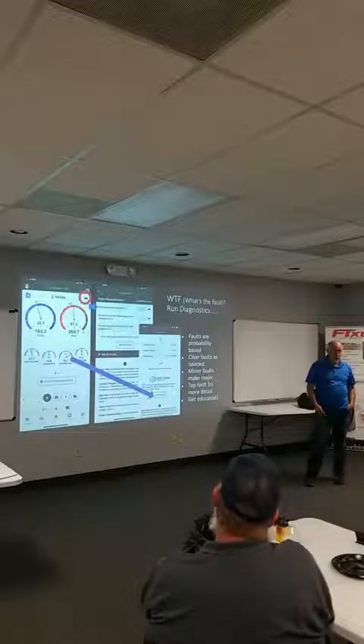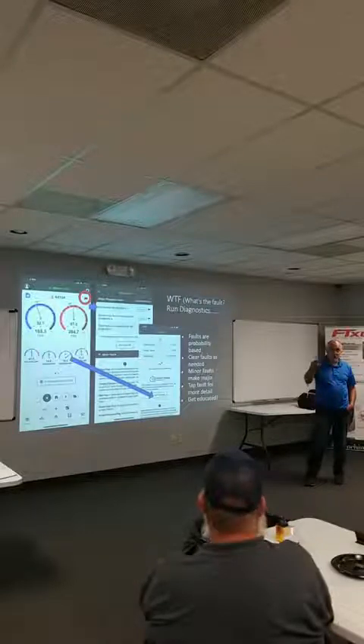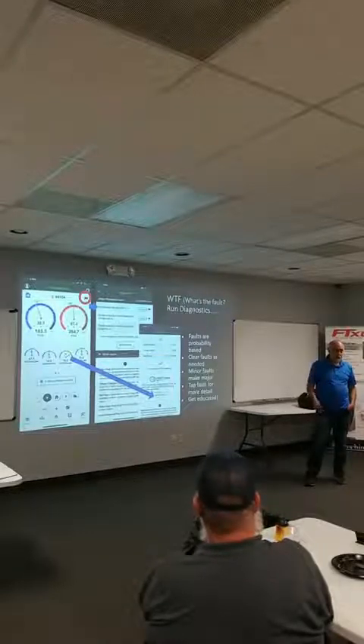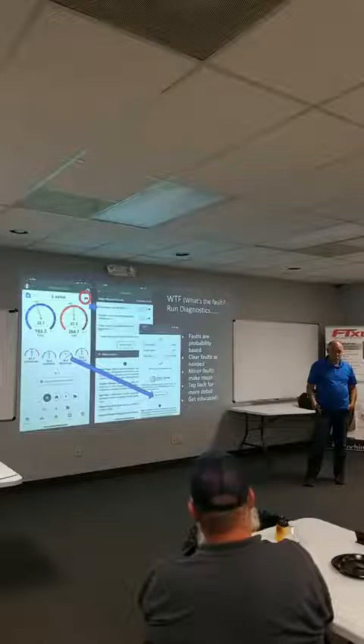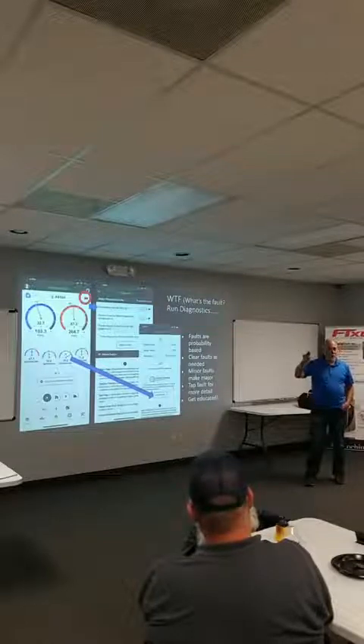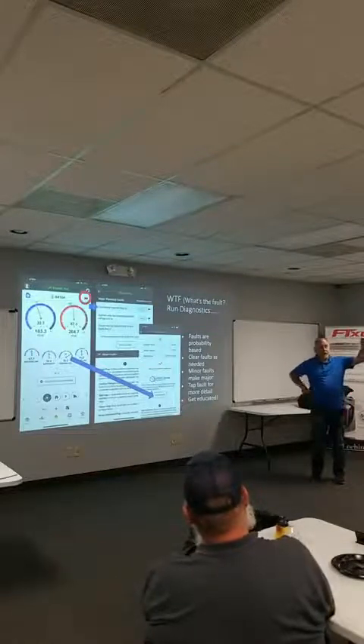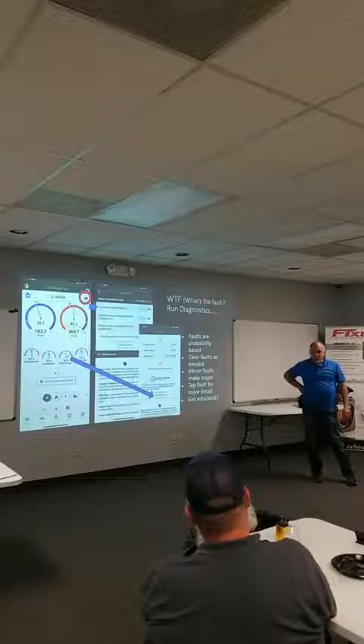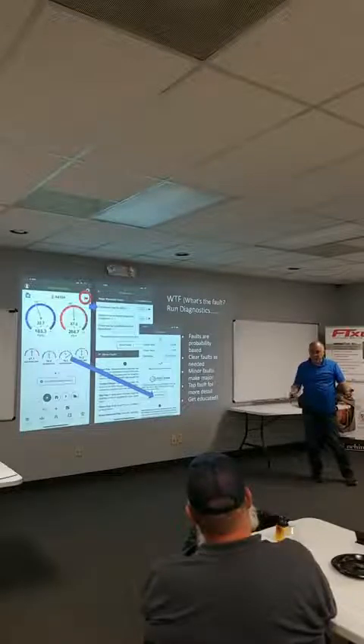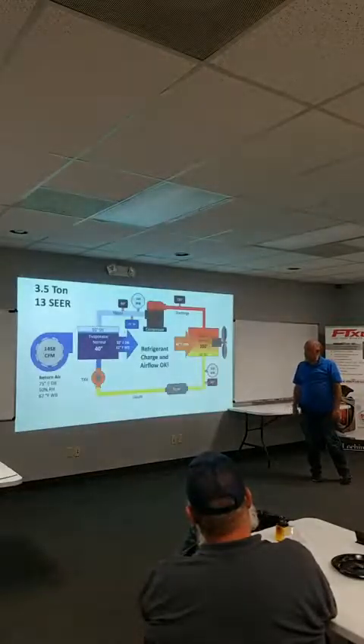You could be going down and pulling the stat off the wall, to see if the hole behind the stat is plugged. You can be popping your head up and seeing what the ductwork looks like, making sure the ductwork is actually connected to the returns and to the supplies, right? Making sure fire dampers are open on the duct system. How many of you have walked into a room and actually reached up and felt that the air's coming out of the registers? It's just stupid stuff. People are hot in offices and uncomfortable all the time because nobody's taken a few minutes to go downstairs and actually check the air delivery system.